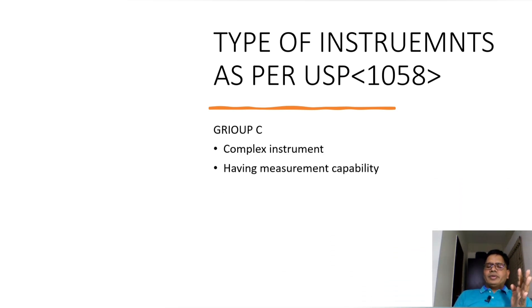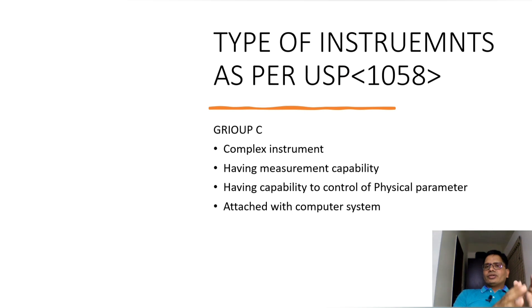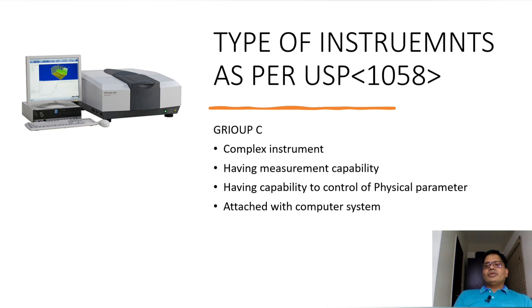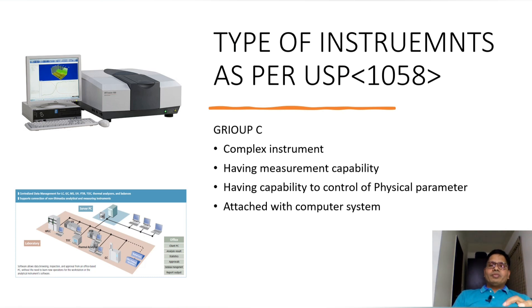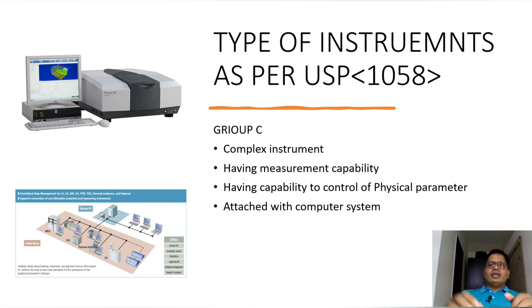Group C instruments are complex instruments that have measurement capability, capability to control physical parameters, and are attached with a computer system. For example, a UV spectrophotometer attached with a computer system comes under Group C. Server-based instruments — where a server exists and different instruments are attached to it — also come under Group C. To summarize: Group A has no measurement capability; Group B has measurement capability and physical parameter control but is not attached to a computer; if it is attached to a computer system, it automatically becomes a Group C instrument.